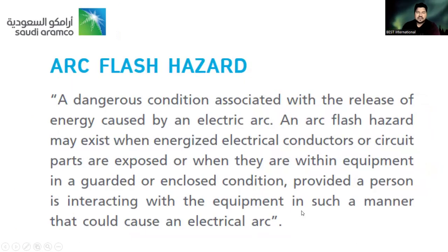So let's talk about arc flash hazards. As I asked you, what is arc flash? So here is some sort of easy understanding as per Aramco guidelines. It's a dangerous condition associated with the release of energy caused by an electric arc. And an arc flash hazard may exist when energized electrical conductors or circuit parts are exposed, or when they are within the equipment and are guarded or in closed condition, provided a person is interacting with the equipment in such a manner that it could cause an arc flash or electrical arc.